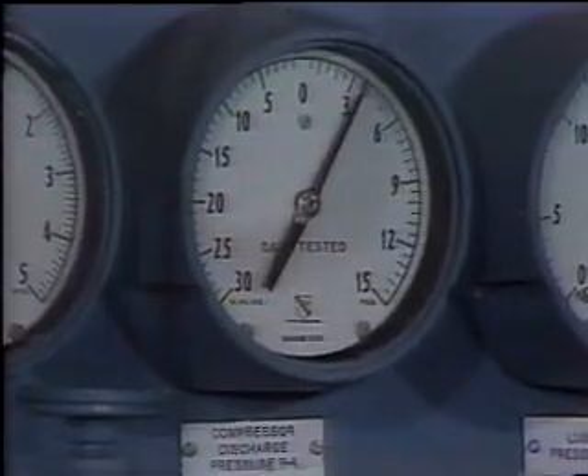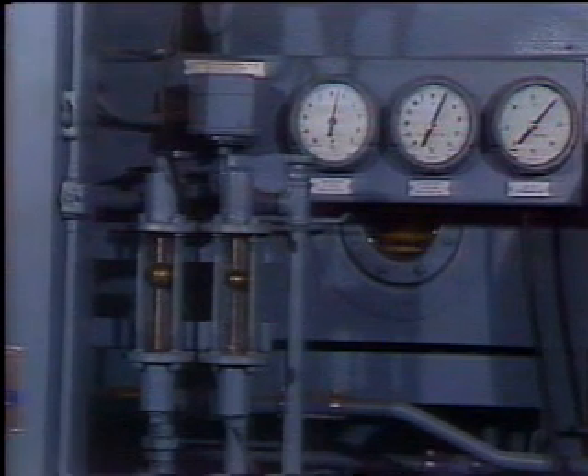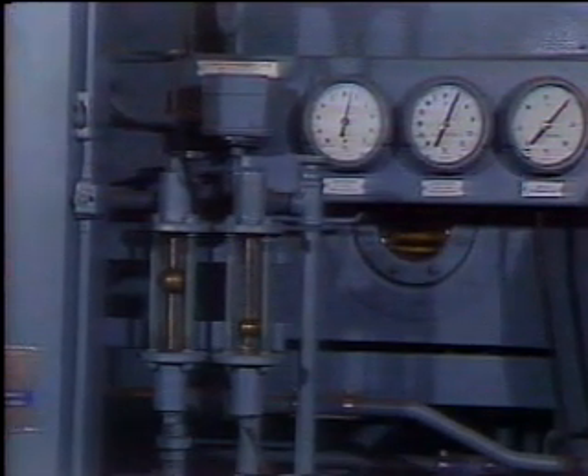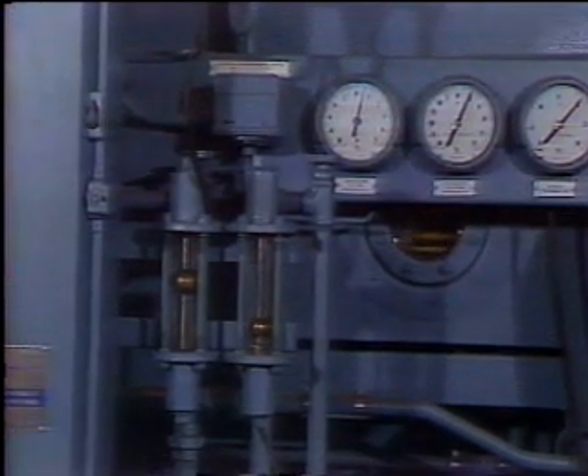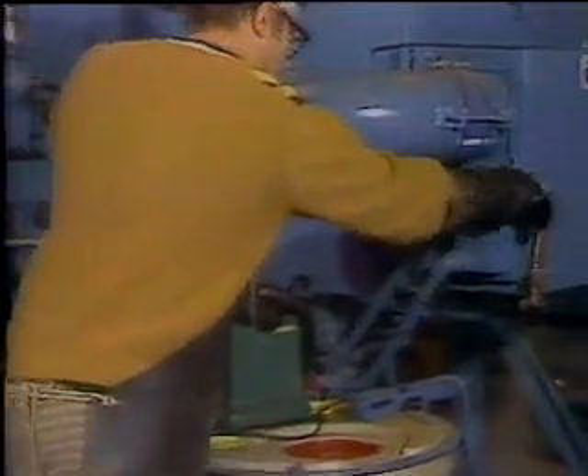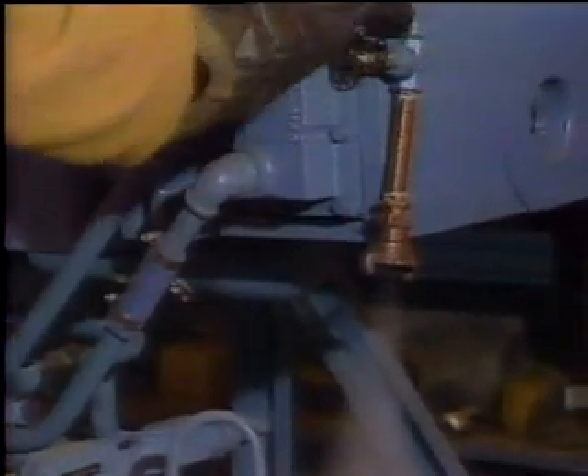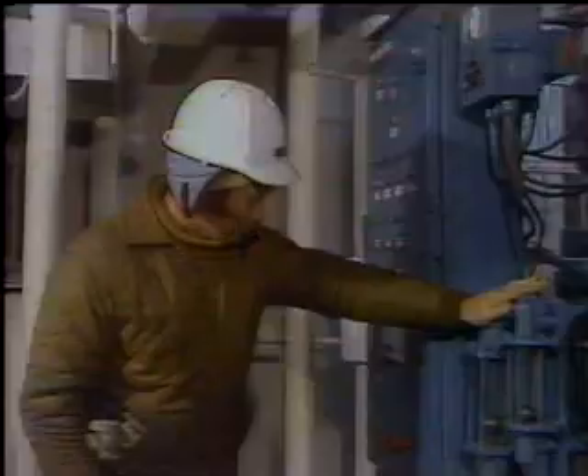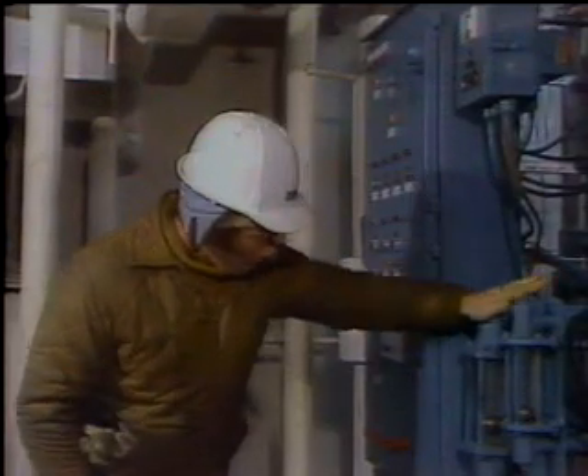If the compressor discharge pressure increases and distillate production drops abnormally, it's probably because of a buildup of non-condensable gases which have accumulated in the tube bundle. This can happen if your vent valve isn't opened wide enough to allow them to escape. Just open the valve for about a minute. This will allow the non-condensable gases to escape. Then close it down to a wisp, but open just a little more than before. This should bring things back into proportion.